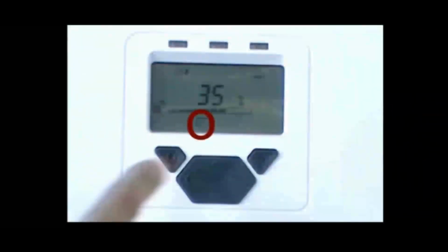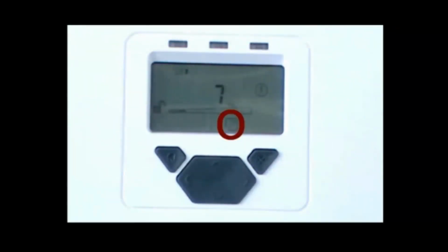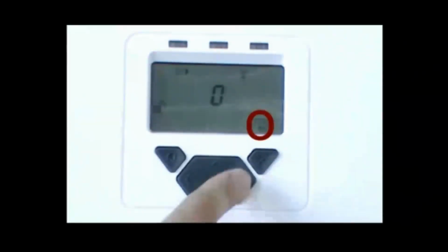There are further settings that can be made. For example, the fire threshold can be set for each detector. The delay to fire and fault can be set for each detector. The system mode can be set to latching or non-latching. Refer to user guide for further instructions. Please refer to the user guide and CD included with the product for further information.